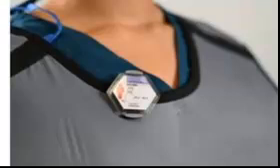The total dose in mGy represents the dose to a point at a specific distance from the focal spot. DAP is a quantity that indicates a combination of dose and the amount of tissue irradiated. It is calculated as the product of the air kerma and the cross-sectional area of the beam, expressed in units of micrograys per square meter or centigrays per square centimeter or rads per square centimeter.